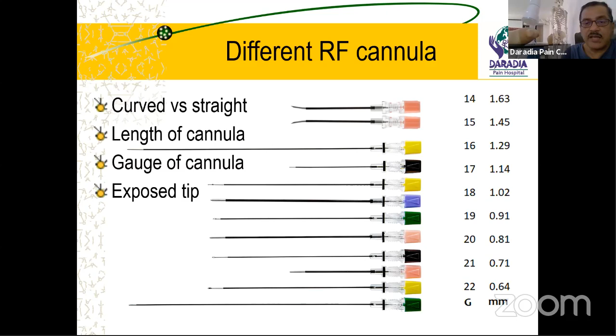The gauge of the cannula can be from 14 gauge to 22 gauge. So depending on your required length and width, there are different varieties. And nowadays there are certain newer cannulas, three different newer cannulas, to have a larger size lesion. So this is a protruding cannula. What is happening here? After putting this needle, there is a side hole through which another needle comes out and it produces a larger size lesion. So this is a comparison between the monopolar, this is a cooled RF, and this is the protruding electrode. And still you can see the cooled radio frequency having the larger size of the lesion.